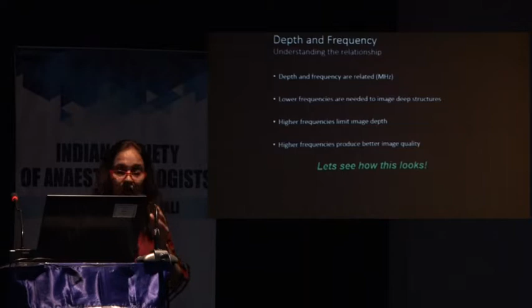Lower frequencies are needed to image deeper structures, and higher frequencies limit the depth but produce better image quality. So the 2 mantras to go back home with are: the higher the frequency, the better the resolution; the lower the frequency, the better the penetration. For a lumbar plexus block, maybe go for a curvilinear probe, or maybe a straighter linear probe, with a mode which is resolution or penetration, which should it be? Yes? Penetration, okay, because it's lumbar plexus.